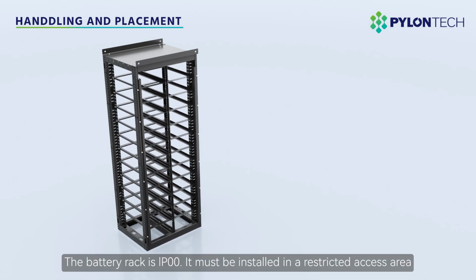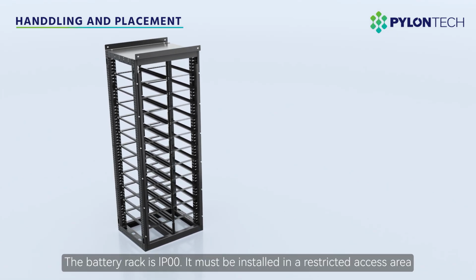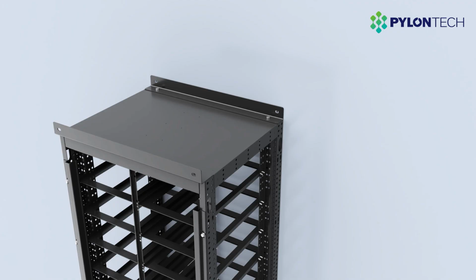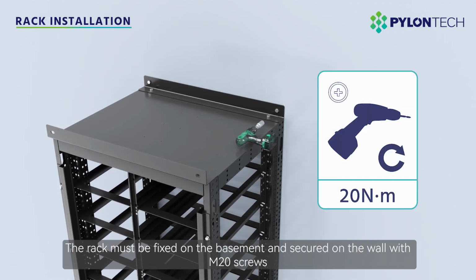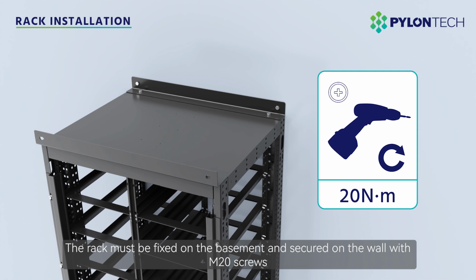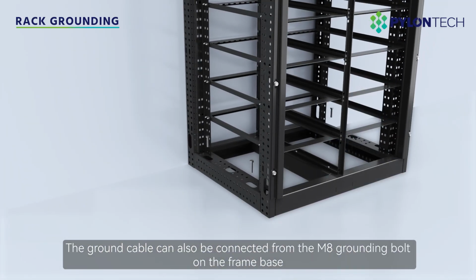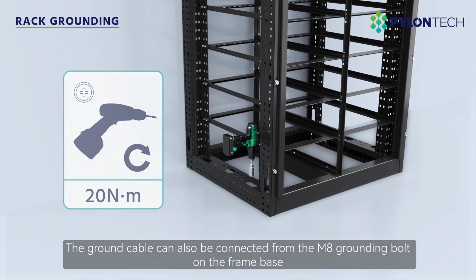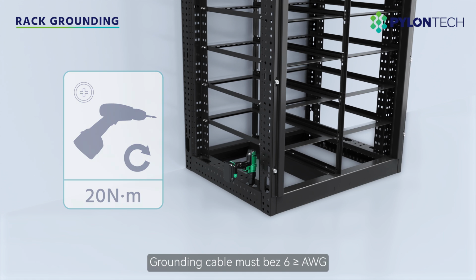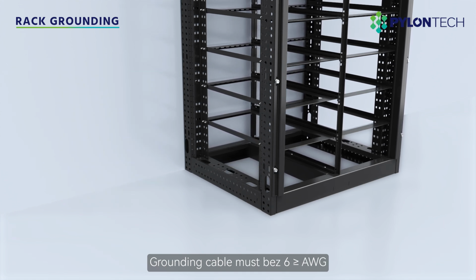The battery rack is IP00. It must be installed in a restricted access area. The rack must be fixed on the basement and secured on the wall with M20 screws. The ground cable can also be connected from the M8 grounding bolt on the frame base. Grounding cable must be greater than or equal to 6 AWG.